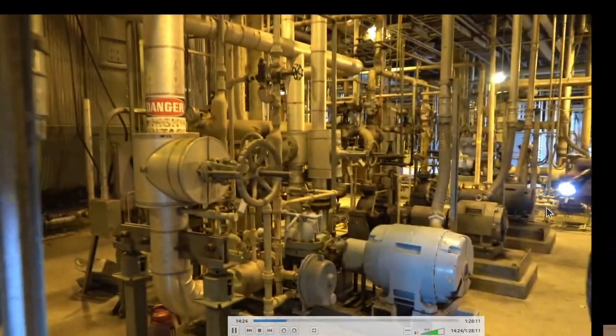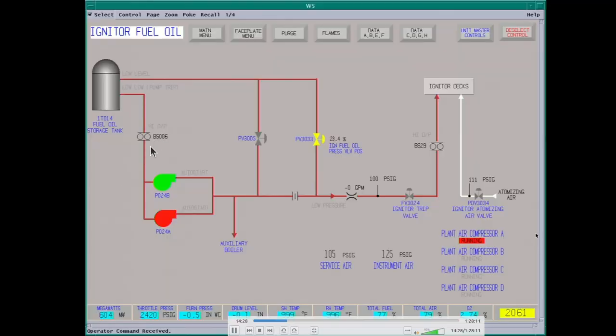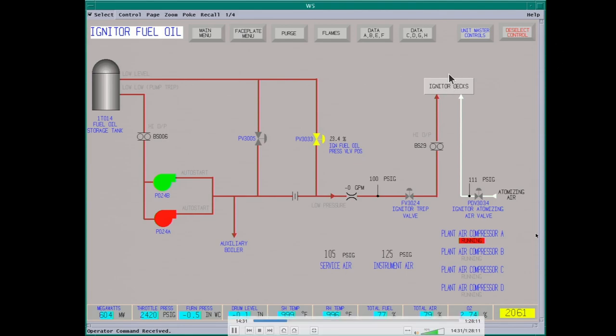These are the pumps for the aux boiler. There are also diesel pumps — these are for the front end of the aux boiler and also the diesel igniters for the coal. This is the igniter fuel oil system — those are two pumps of a fuel tank. It feeds your igniters primarily, and also it feeds the aux boiler. Each igniter burns about three and a half gallons a minute, and you've got four igniters per deck.